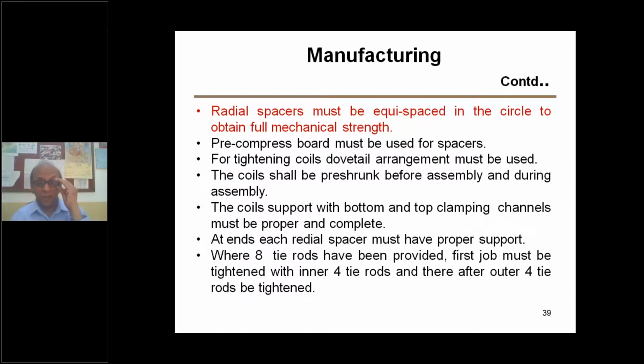So pre-compressed board, yes, you can use it, or proper opening and tightening is to be done. For tightening coils, a dovetail arrangement must be used, so they are fixed in a proper position. Coils shall be preshrunk, yes, that is true. Coil support with bottom and top clamping channel must be proper and complete. Each channel and the inside of the core yoke must be properly insulated. This will not cause failure, because of very small cost. At the end, each radial spacer must have proper support, from the channel or fasteners.